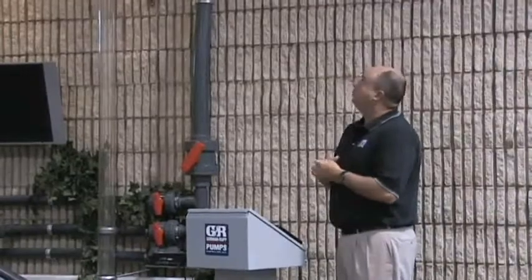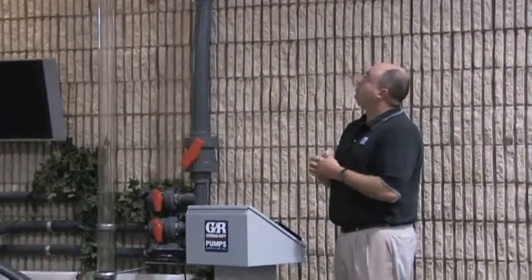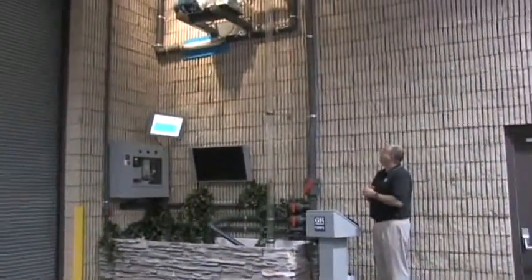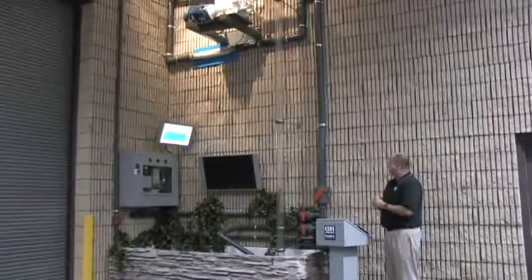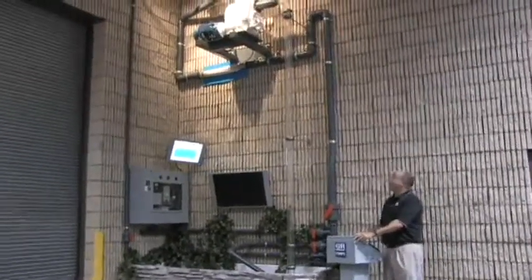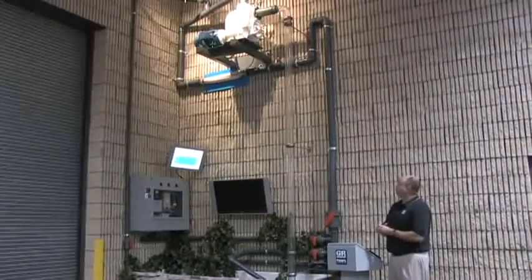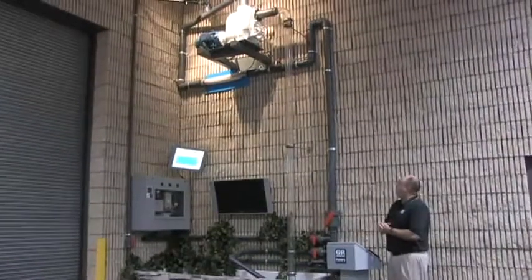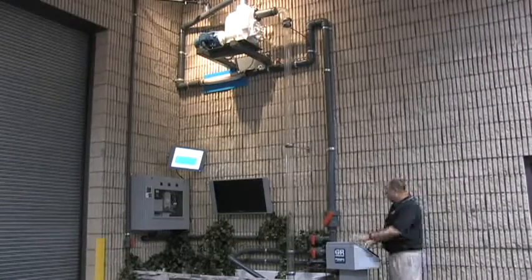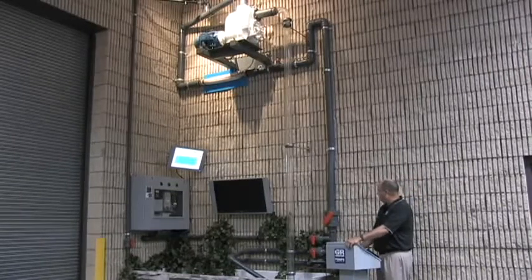So to demonstrate that, I'm going to start the pump up here, and we'll just see how quickly this pump can prime itself on a 15-foot lift at 1750 RPM pump speed and a 3-inch suction line. So we'll go ahead and start that up, and then when I stop the pump from running, you'll see also the water falling down the suction leg, but also water siphoning out of the pump casing. So let's run through that demonstration here real quick.